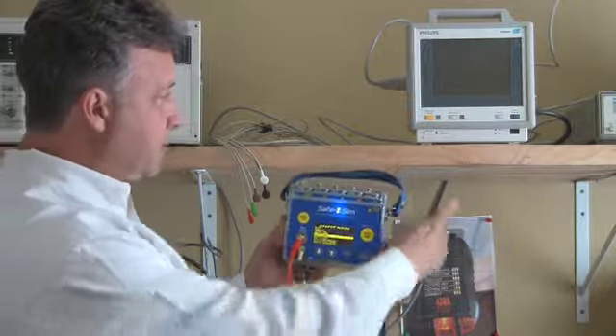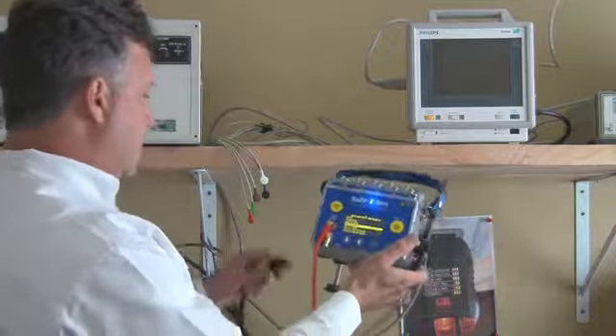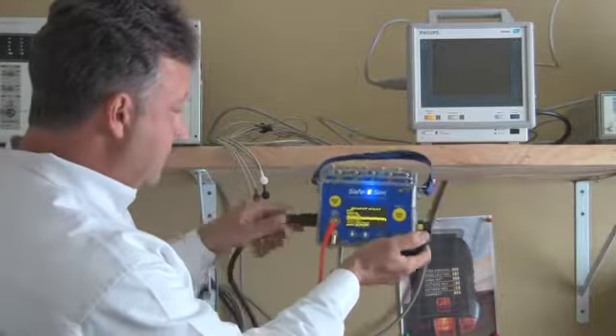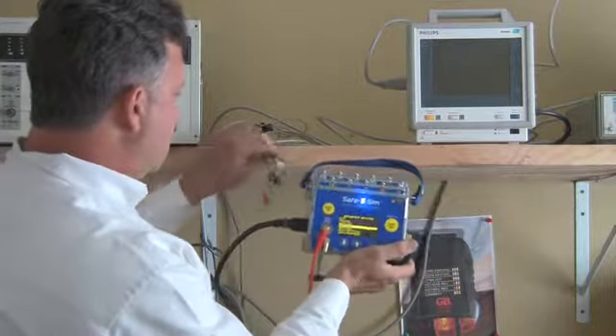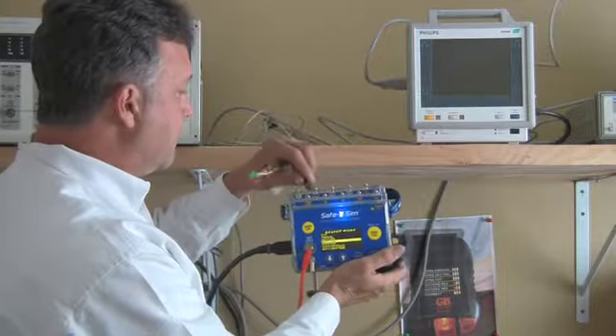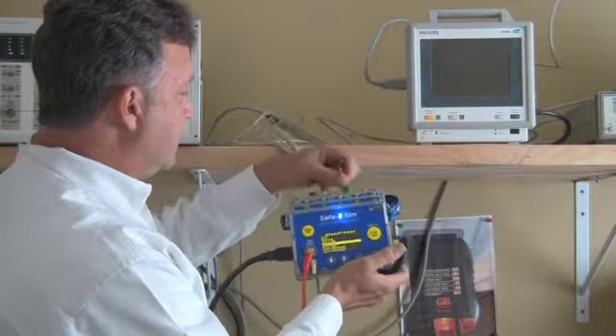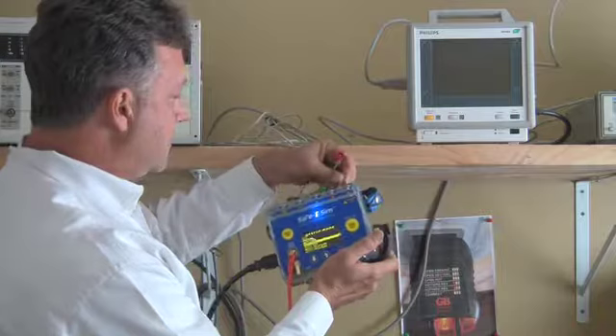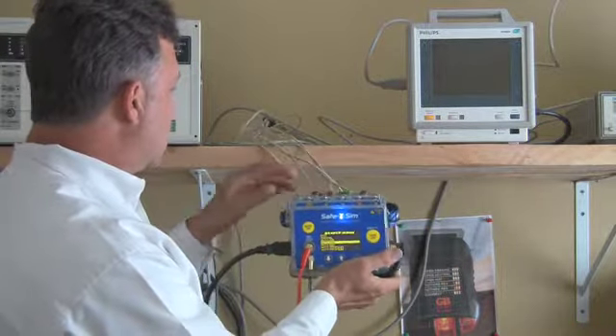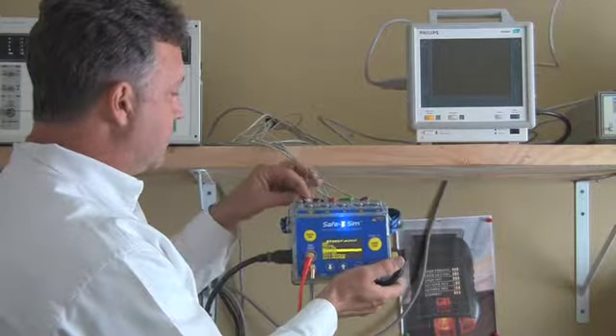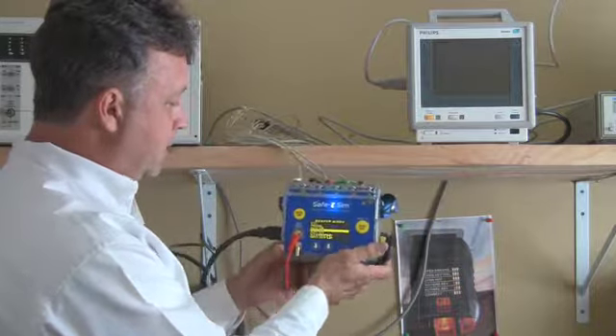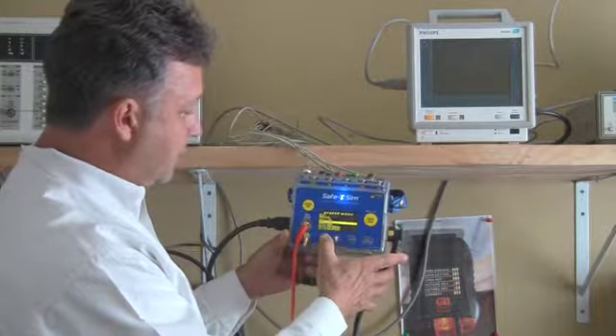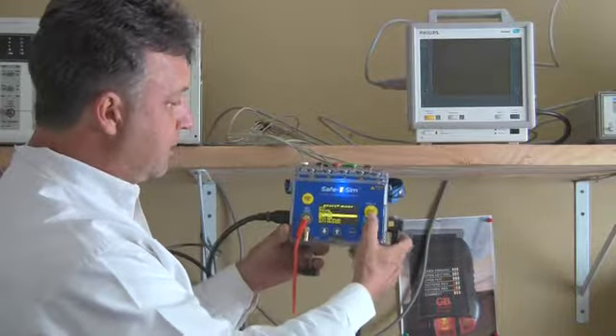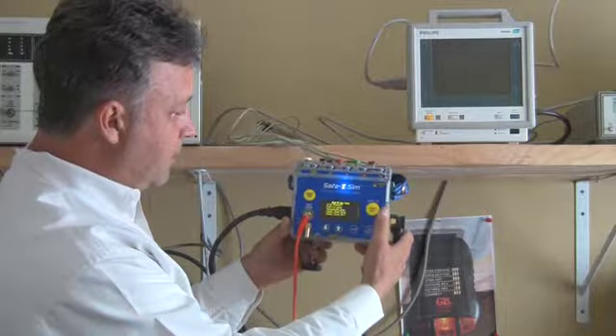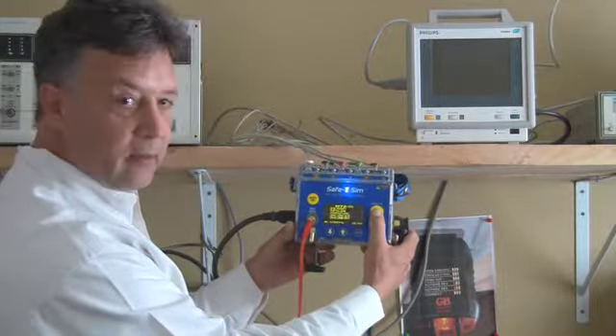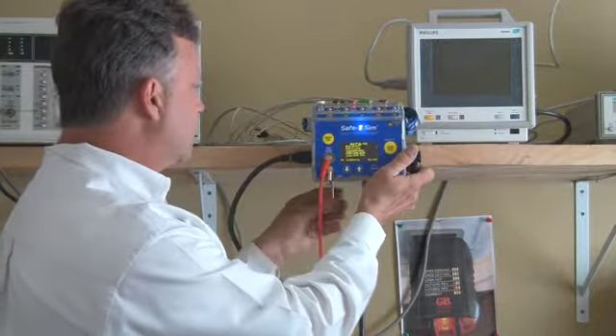If I run a test right now on this patient monitor, we can actually do an electrical safety test and a simulation on it. I'm going to plug in the power cord for this device into the DUT power outlet on the safety analyzer. Now I'm going to hook up my ECG leads ahead of time. Those are color coded, so you've got a much easier time hooking those up. In this case, I'm only going to use 5 leads, and we're ready to go. So I'm going to select the ES2 electrical safety test, and I'm going to show you a couple of unique features with the device. If I hit enter, I get the home screen for that auto test. I'm going to go ahead and clamp this down here so you can see it a little bit better.